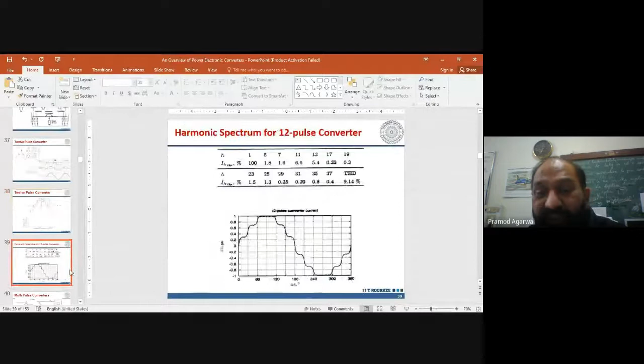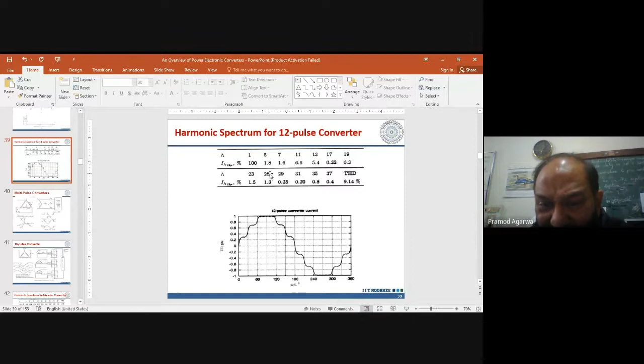This is the practical 12 pulse converter waveform, and you can see the fundamental. Basically, it should have 11th and 13th. The fifth and seventh, a very small amount you are getting because of the transformer action; your current is different from the ideal one. 17th and 19th are also negligible, but the 23rd and 25th, yes, they are present.